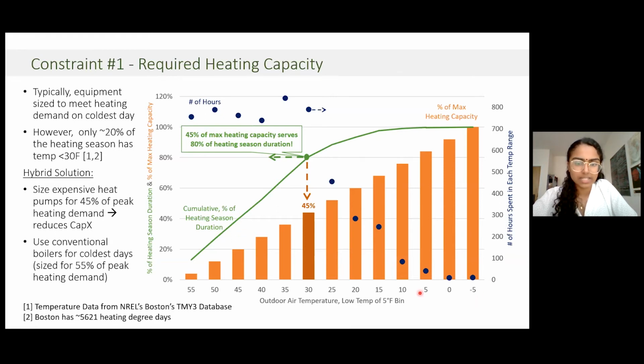So what we asked ourselves is, is there a way that we could design a system that includes heat pumps and boilers to take advantage of when most of the heating energy will be used, and size our more expensive and more efficient equipment for that point, and use boilers for those coldest days. And so what we determined was that we can have our 30-degree temperature be our switching point. So we find that if we install heat pumps for temperatures that are greater than 30 degrees Fahrenheit, we would install 45% of our peak heating capacity with heat pumps, and this would service 80% of the heating season duration.